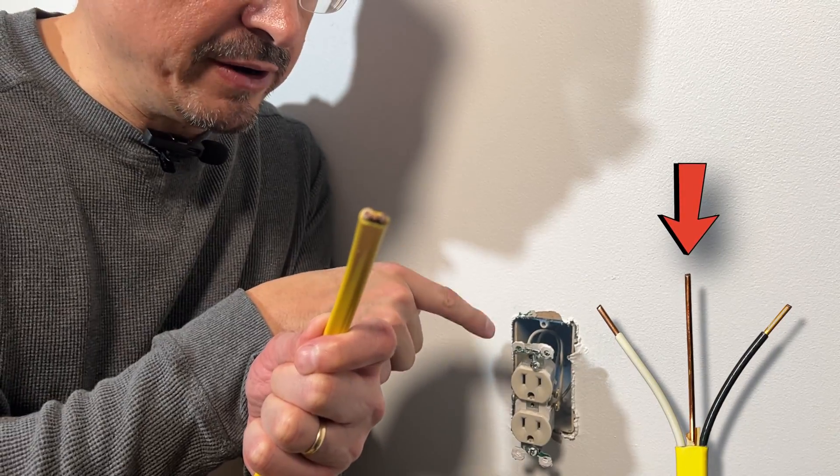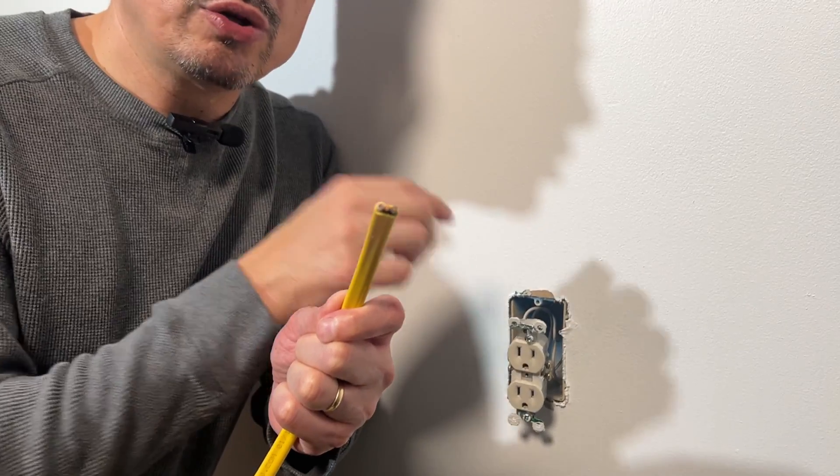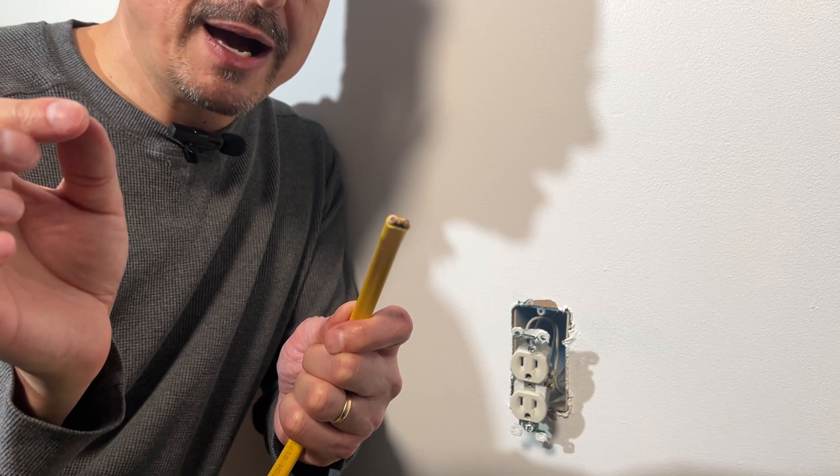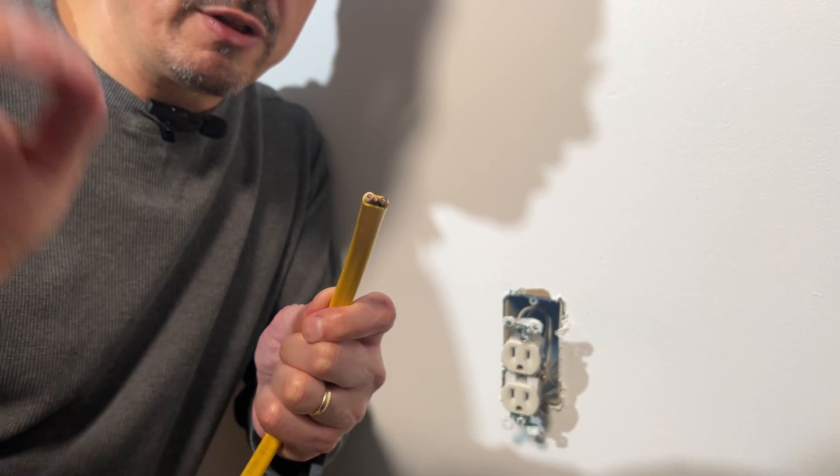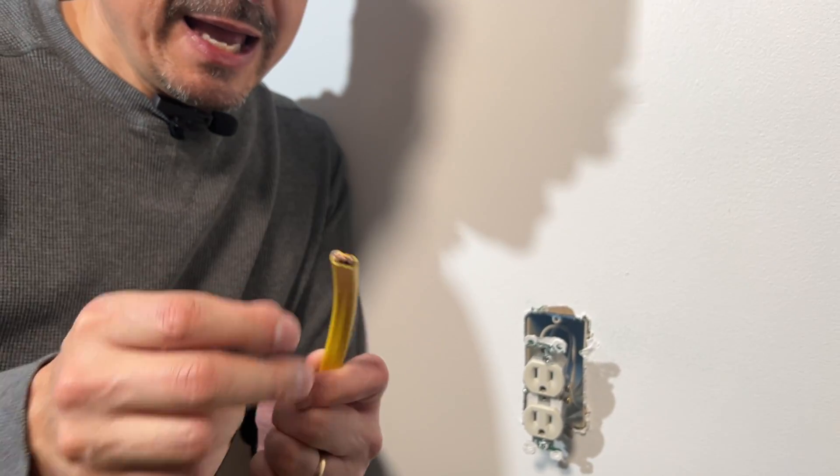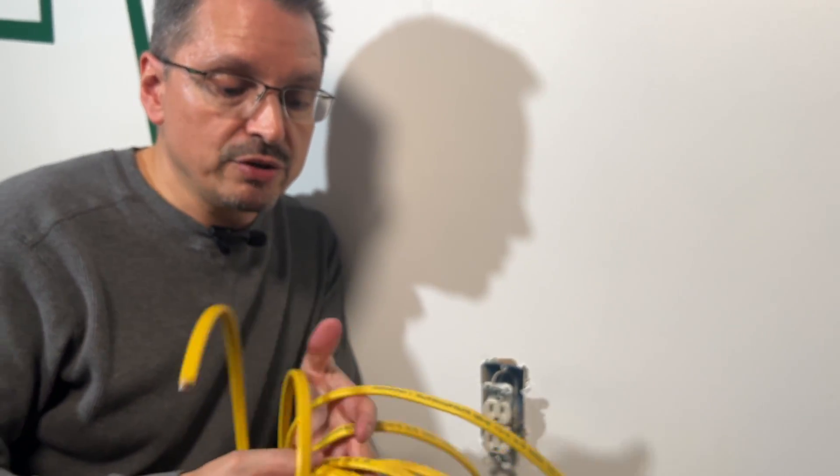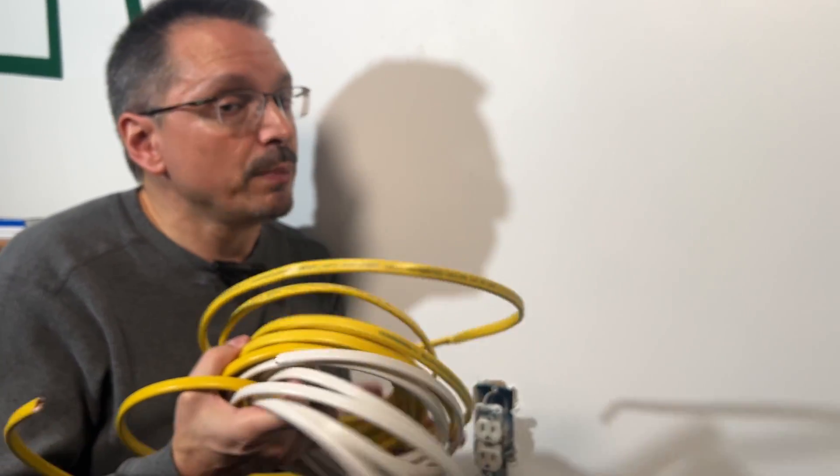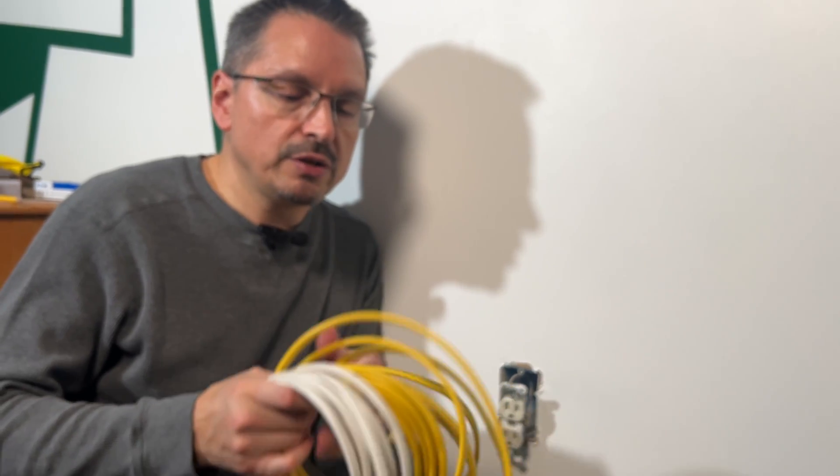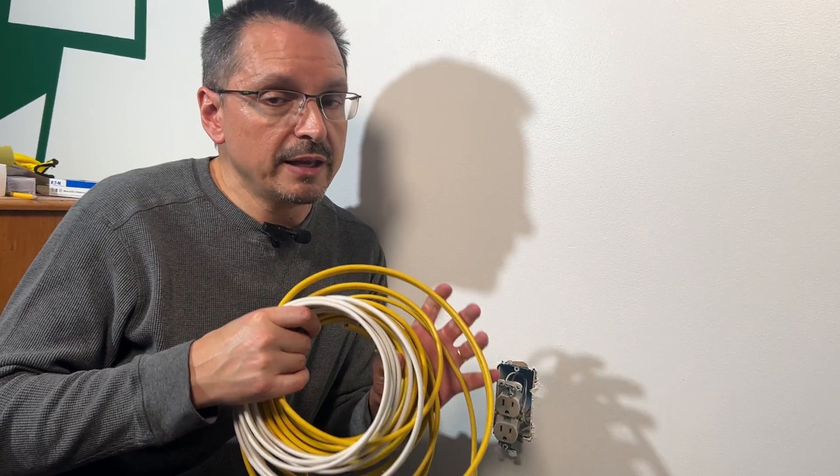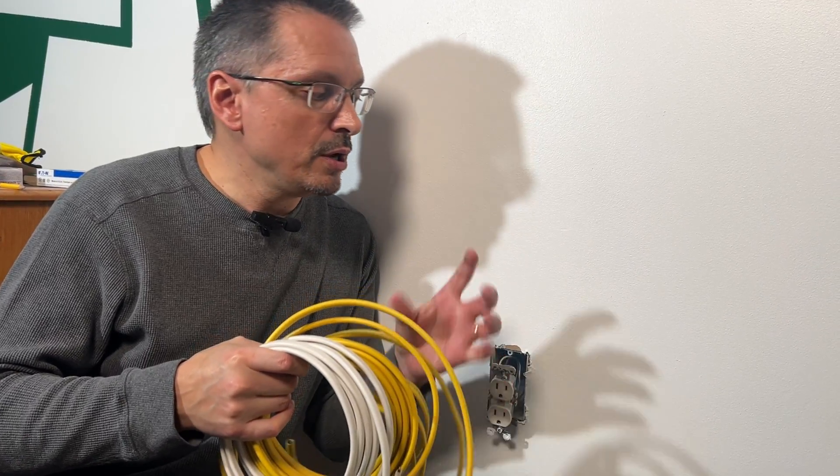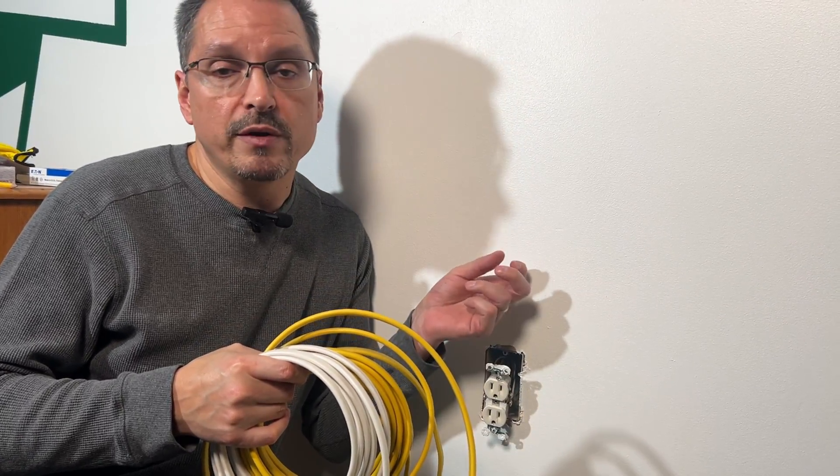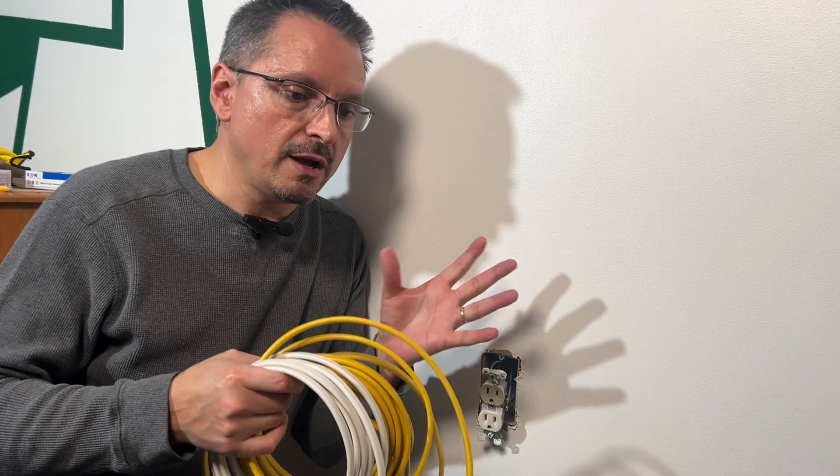That bare copper wire is all you need to ground this. It has to go to the main panel box, grounding bus bar, which then goes to the earth ground rod. It is expensive and difficult, as you imagine, to run all new wiring throughout the house, but it is an option. You may want to reserve that option unless you're doing a total renovation or maybe you're removing old plaster and drywall to the studs.